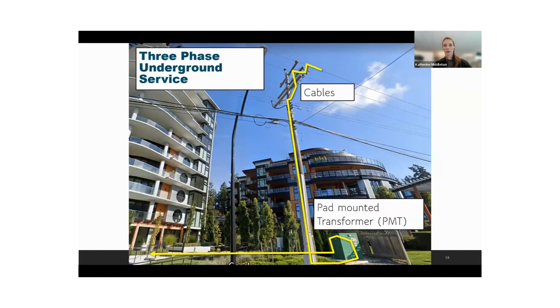I've got here an example of a three-phase service coming from an overhead line to an underground transformer, or pad mount transformer. Before, the transformers were located on the pole. Here, this transformer, that green box, is located beside the pole or in a location close to where it's going to be serving the load. And so the service for this building, a higher rise building, is being fed from this transformer.